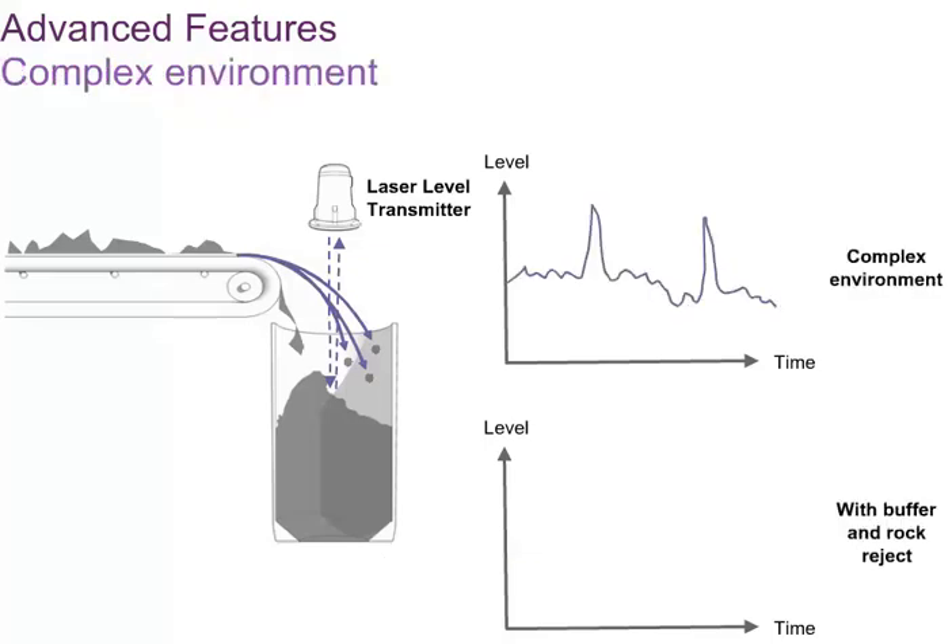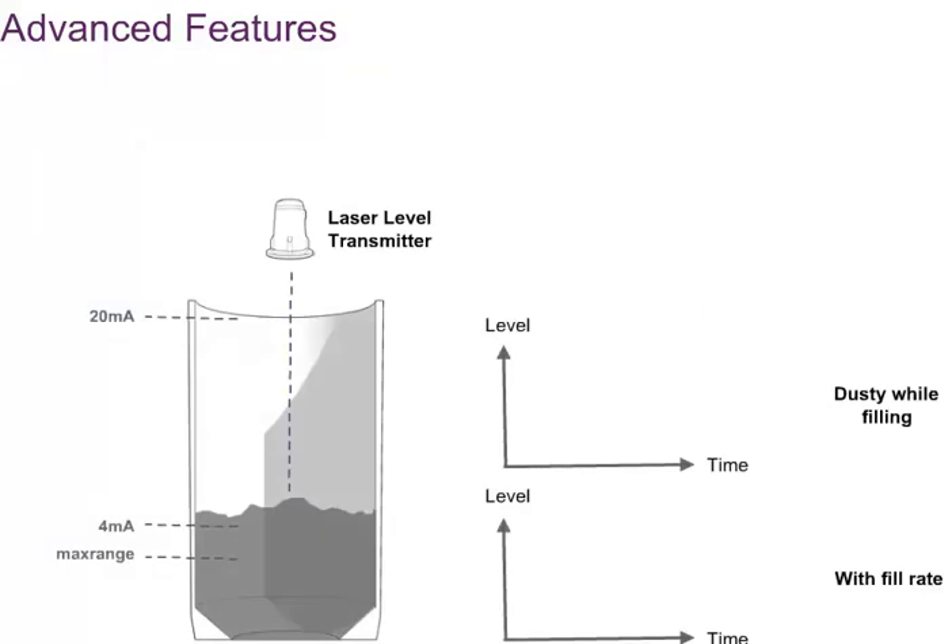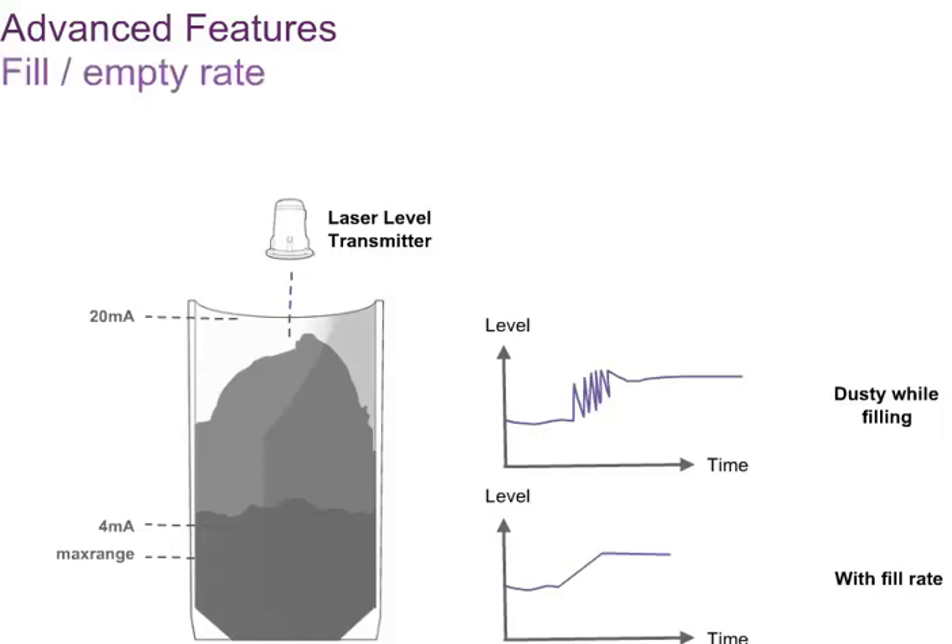In complex environments, the rock rejection and buffering features can be used together to both smooth the response and eliminate rapid transients. An example of such a complex environment would be the surface of a liquid with constant waves and splashing drops. In some applications, the granular solid material is loaded into or unloaded from the storage vessels in batches, which can generate considerable amounts of dust. If you cannot see the surface through this dust, then the instrument may fail to measure the true level of the surface. To deal with this batch loading condition, fill rate and empty rate settings found in the advanced menu can be applied. These limit the rate of rise of the surface artificially until the dust clears and the instrument can correctly measure to the surface.